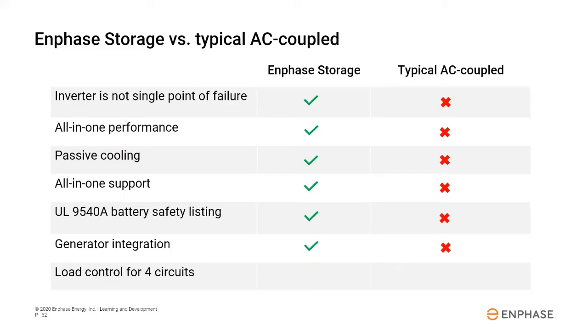Advanced integration with generators, which allows them to operate together with solar and storage for maximum power and the ability to charge batteries with the generator. And then load control for multiple circuits, even sub-panels, compared to other systems which can typically only control a single thermostat-controlled load.